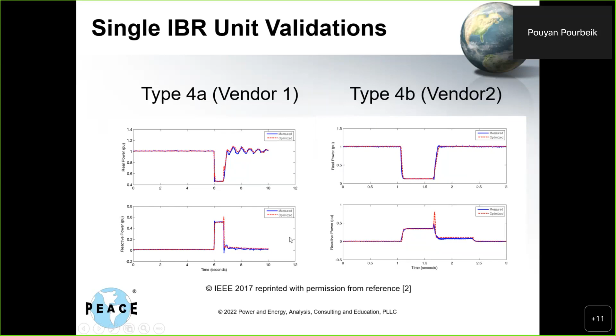These are IEC tests done at the terminals of an individual inverter, and you see the response in blue, measurement, real power up top, reactive power on the bottom. We're putting fictitious faults at the terminal of the machine or inverter, and the simulated response is in red. In these cases, the simulated runs are from parameterized standard models, not black box - these are written models, and it's a good fit. I'm only showing you one, but there were dozens of voltage dips done with the same parameters and pretty good fit across all of them.